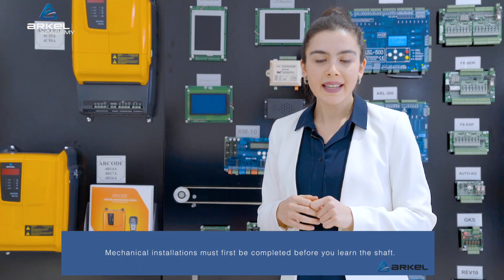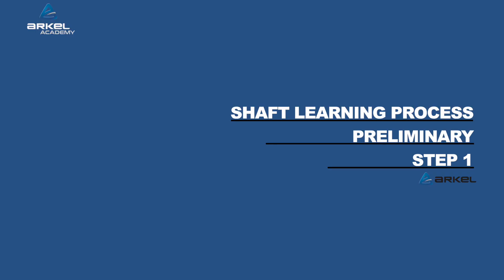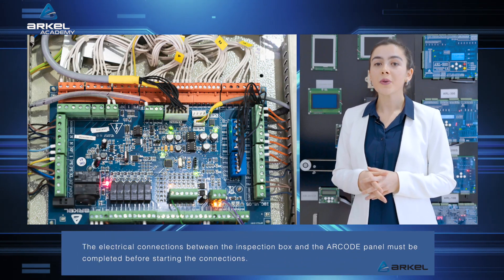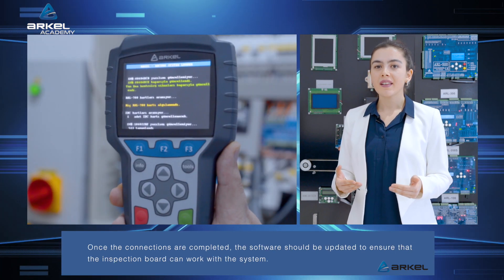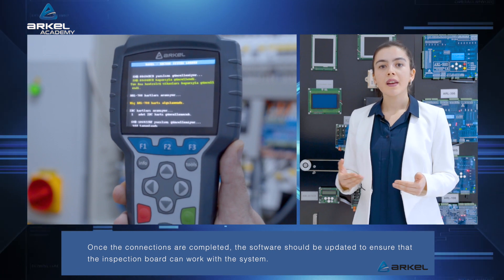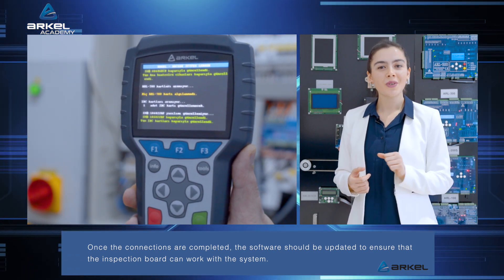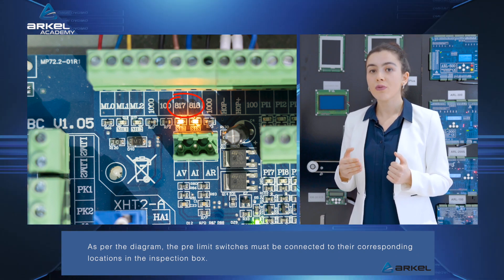Mechanical installations must first be completed before you learn the shaft. Shaft learning process – preliminary: The electrical connections between the inspection box and the ARCODE panel must be completed before starting the connections. Once the connections are completed, the software should be updated to ensure that the inspection board can work with the system. As per the diagram, the pre-limit switches must be connected to their corresponding locations in the inspection box.